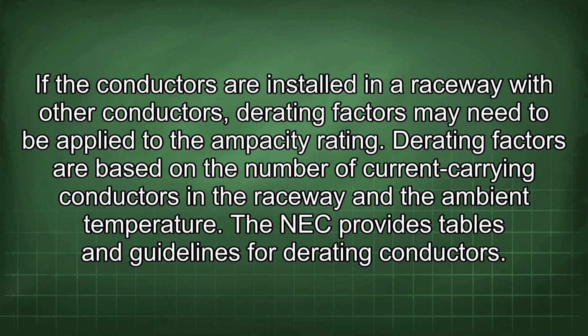If the conductors are installed in a raceway with other conductors, derating factors may need to be applied to the ampacity rating. Derating factors are based on the number of current carrying conductors in the raceway and the ambient temperature. The NEC provides tables and guidelines for derating conductors.